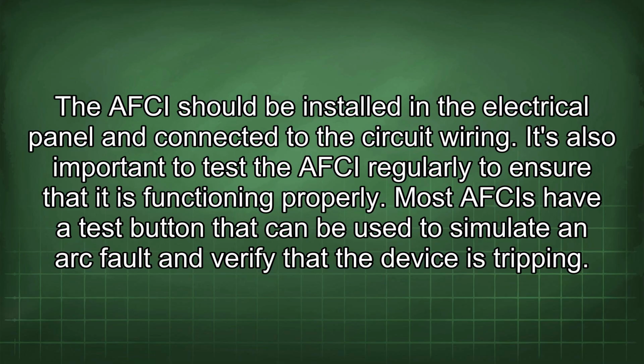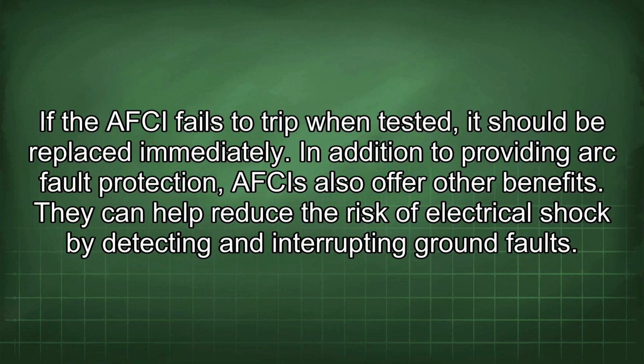It's also important to test the AFCI regularly to ensure that it is functioning properly. Most AFCIs have a test button that can be used to simulate an arc fault and verify that the device is tripping. If the AFCI fails to trip when tested, it should be replaced immediately.